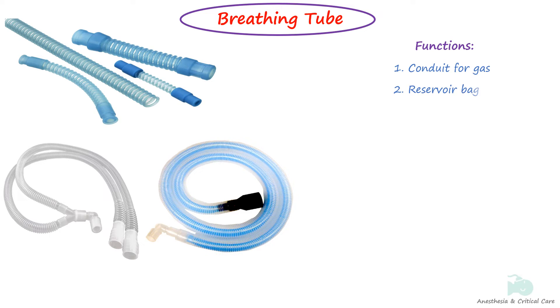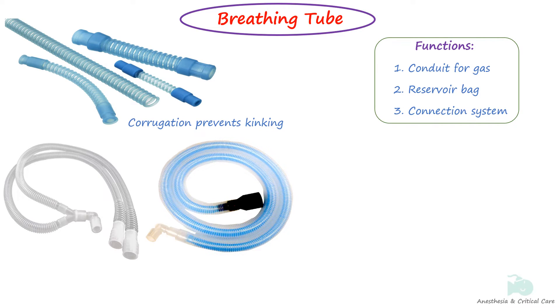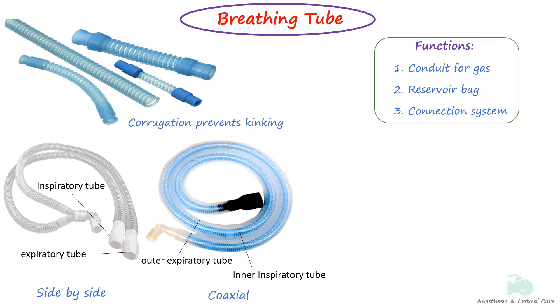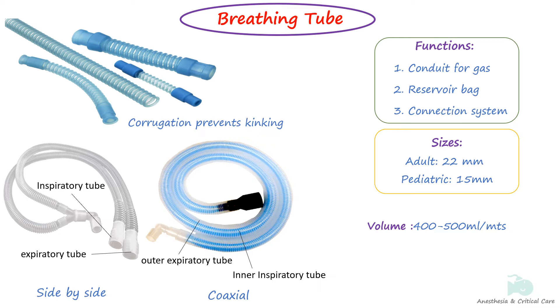Breathing tubes are hollow structures that serve as a conduit for breathing. The tube functions as a reservoir in certain systems and provides connection from one part of the system to another. They are rubber, plastic, or silicone tubes and can be impregnated with silver to add antimicrobial effect. The corrugated build prevents kinking and increases flexibility. They may be side by side or coaxial. The internal diameter is standardized: 22 mm for adults and 15 mm for pediatrics. They usually have an internal volume of 400 to 500 milliliters per meter.